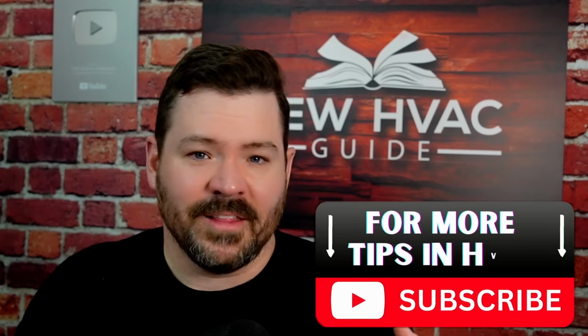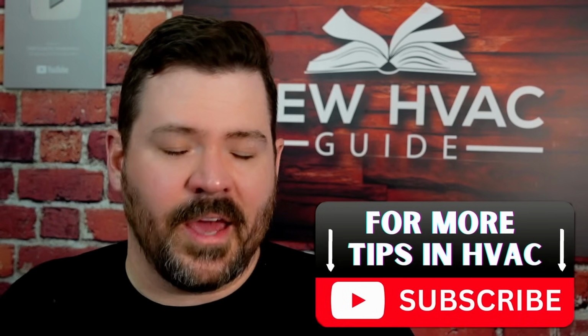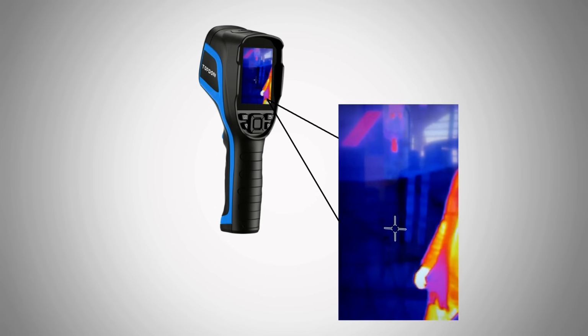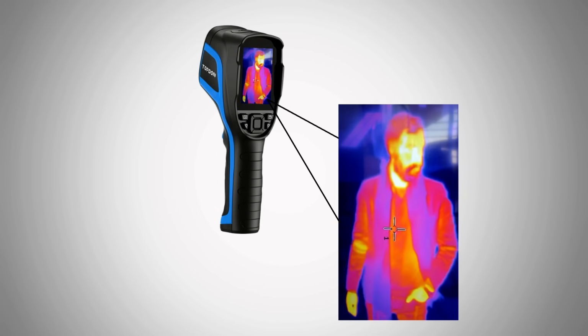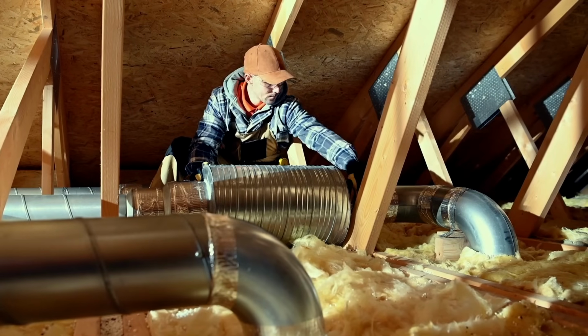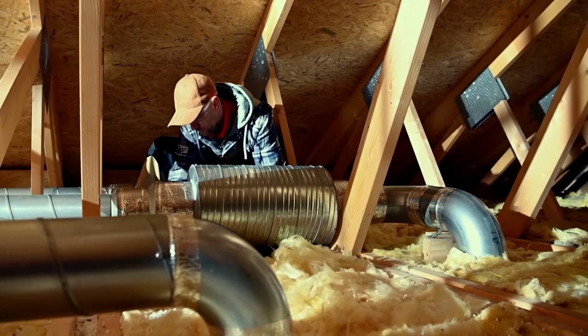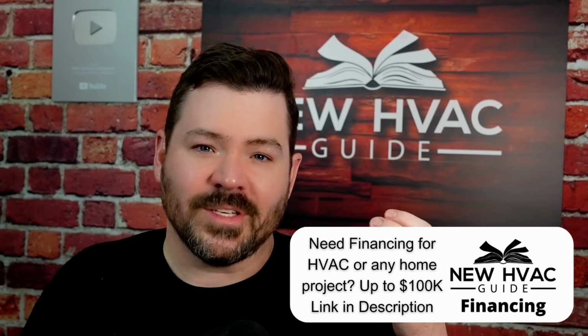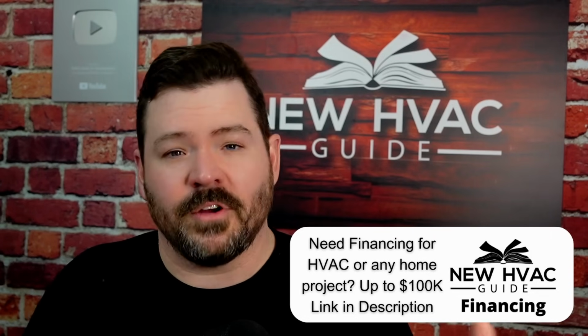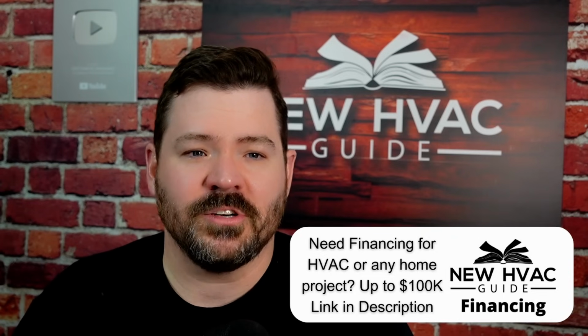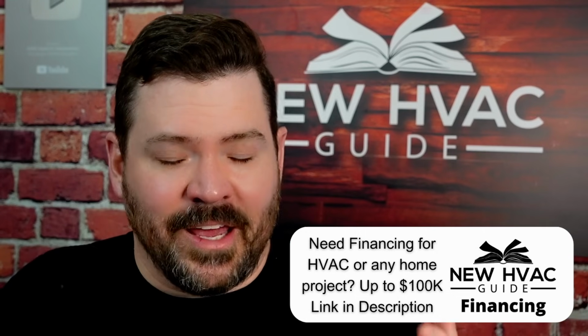I personally, at my heating and air business that I ran for 12 years before selling it, had customers tell me, yeah, this system doesn't do as well as I'd like it to. Let's just up the size on it, without doing a load calculation, without addressing the home properly, without running a thermal camera or having a building science expert audit the home. They'll just simply buy a bigger system that will possibly be oversized for the ductwork, cause issues with overall sizing, short cycling, and all the other ins and outs of properly sizing the heating and air system.